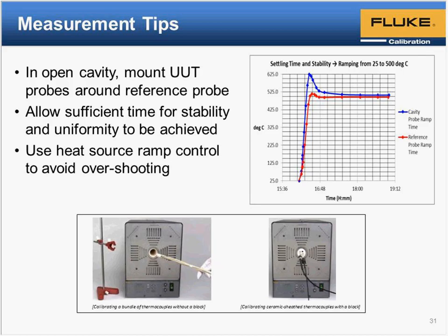Here are some tips to consider when you are using equipment like thermocouple furnaces. First of all, keep in mind that the curves over here show that stability arrives before uniformity does in a furnace. Here's an example of two probes that were put inside a furnace like the one shown here. They're close to each other, but in slightly different locations, and the control probe is in red.